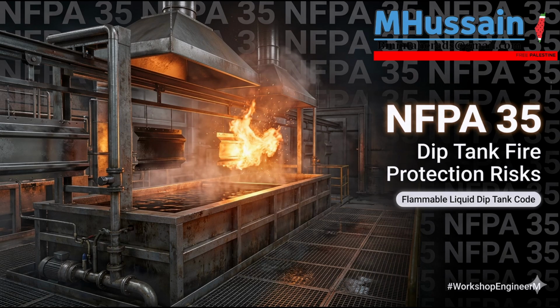Smothering is completely ineffective. So what do you do? The only way to stop a nitrocellulose fire is through massive, overwhelming thermal extraction. You have to use an immense volume of water to forcefully pull the heat out of the reaction, dropping the temperature below the ignition point faster than the chemical decomposition can generate new heat. That requires a literal deluge. Yes. That makes the stakes so high.